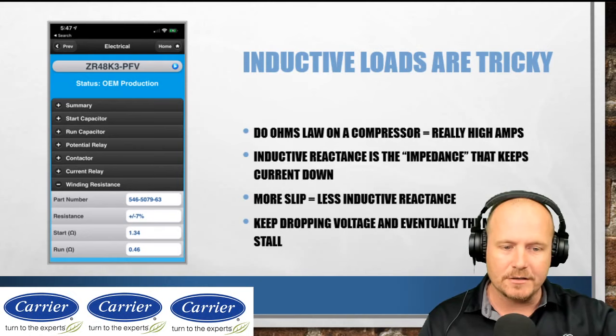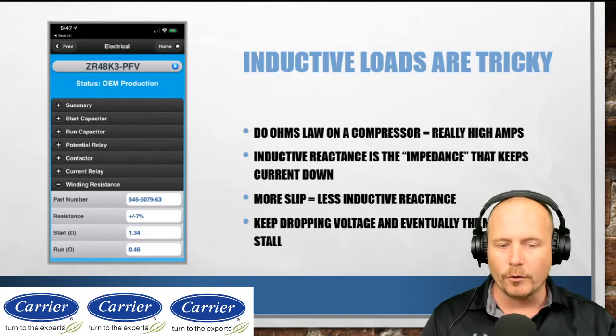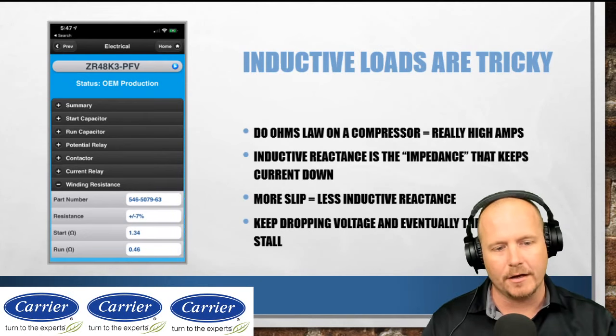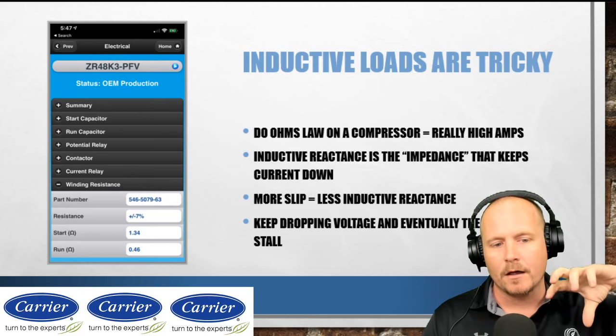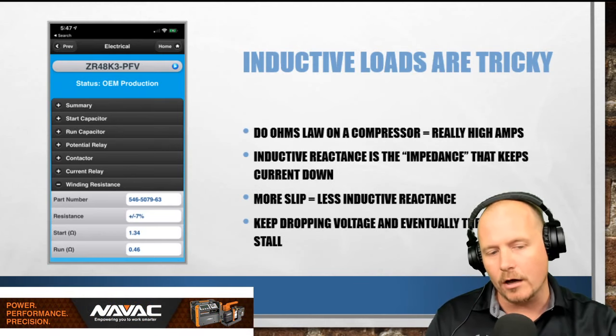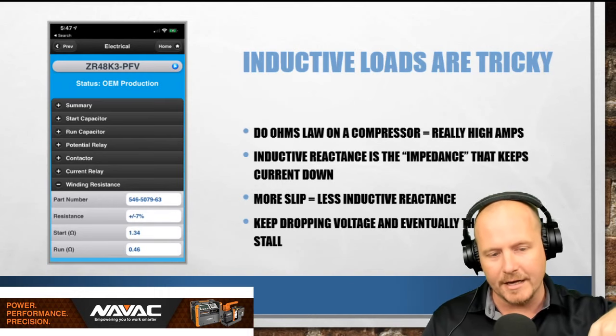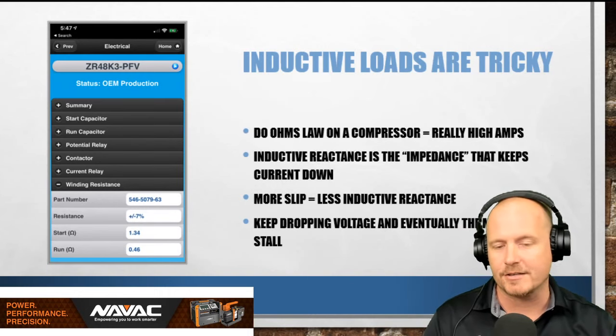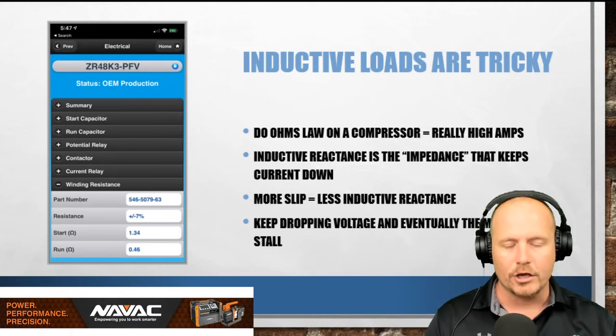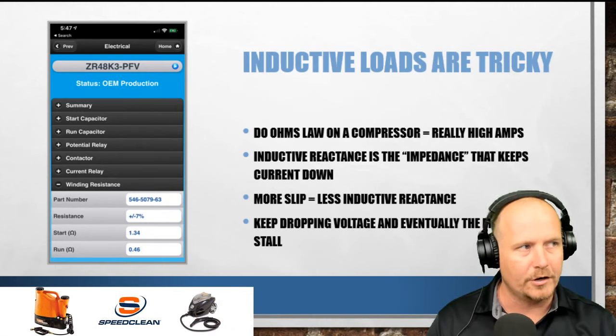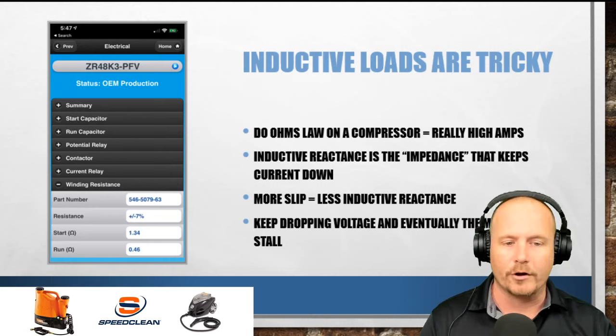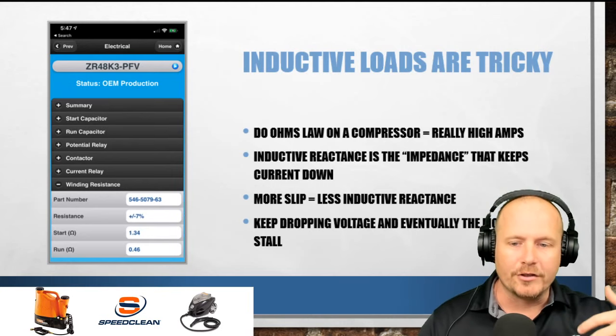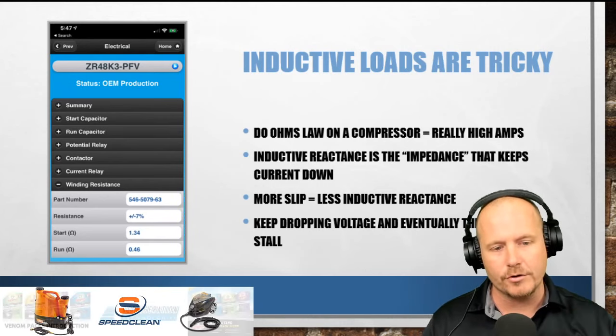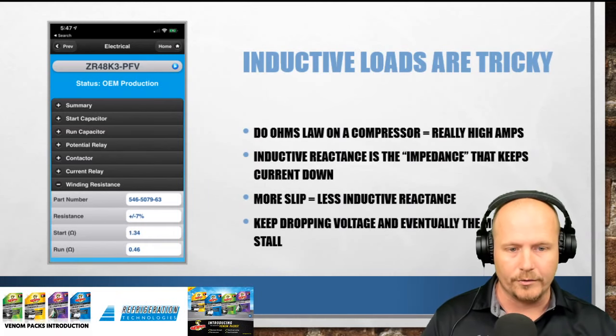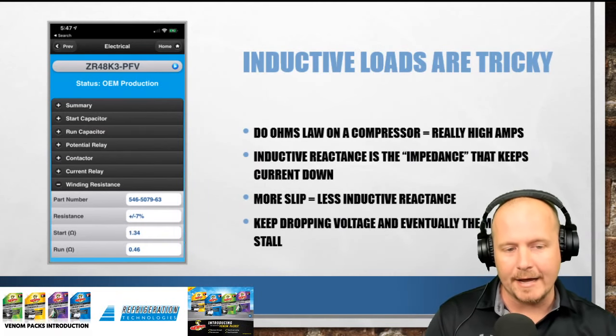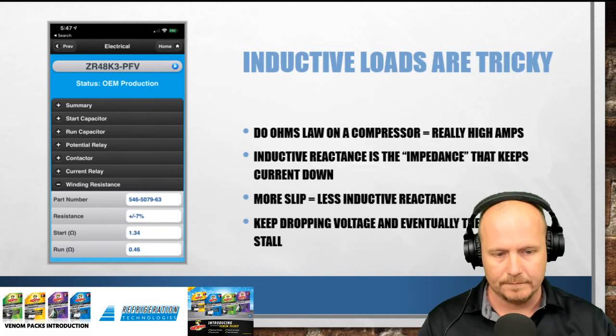But by the time it gets to the point that it does stall, your voltage, at least in my testing, and it depends on the load the motor is under, is going to be so low that even then your current will tend to be on the low side. And again, this is a curve. This isn't linear. Every different motor would be slightly different, and you would have to test them independently in order to know what the result would be. So the answer to that question, what happens when you reduce the voltage on an inductive load on a motor? In many cases, the amperage still goes down.